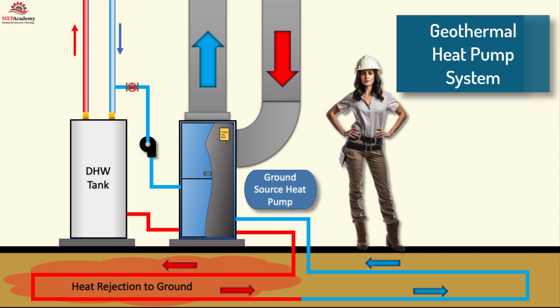A desuperheater can be used in conjunction with a geothermal heat pump to provide additional hot water heating capabilities. In a geothermal heat pump system, the desuperheater utilizes excess heat generated during the cooling cycle to heat water for domestic use. Here's a general overview of how a desuperheater works with a geothermal heat pump.